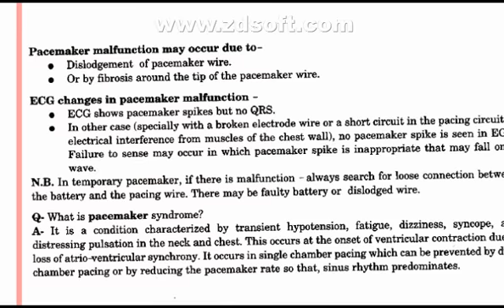ECG shows pacemaker spikes but no QRS. In other cases, especially with a broken electrode wire or a short circuit in the pacing circuit or electrical interference from muscles of the chest wall, no pacemaker spike is seen in ECG. Failure to sense may occur in which pacemaker spike is inappropriate that may fall on T wave. In temporary pacemaker, if there is malfunction, always search for loose connection between the battery and the pacing wire. There may be faulty battery or dislodged wire.